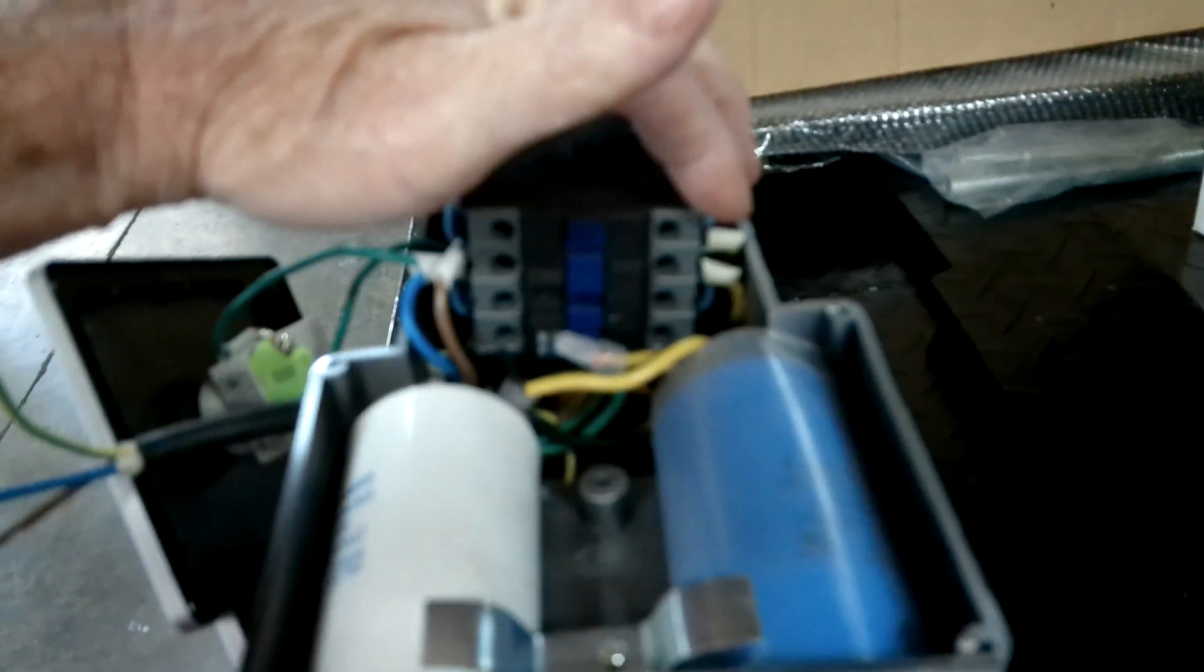And then when the contactor senses power, when you push in the button, it will energize the coil on the contactor and it will pull that in. So this little blue thing is going to suck in, and then that will give you electricity across those two contacts. In this case, it's going to be two wires here, two wires there, and those two contacts, when that pulls in, you'll have 220 volts coming in and 220 volts going to the motor. That is basically how that's going to be wired up.